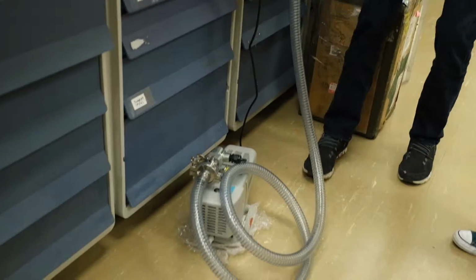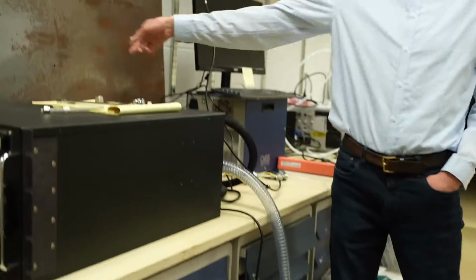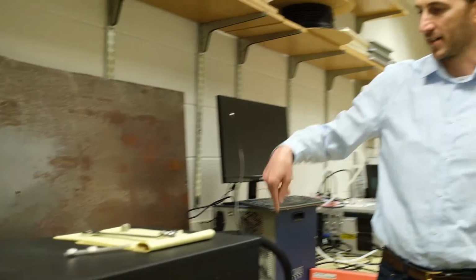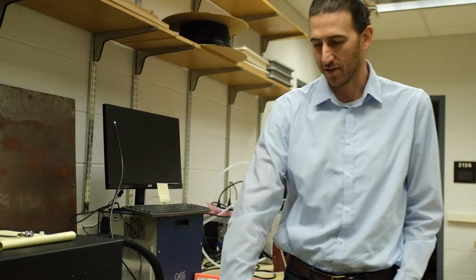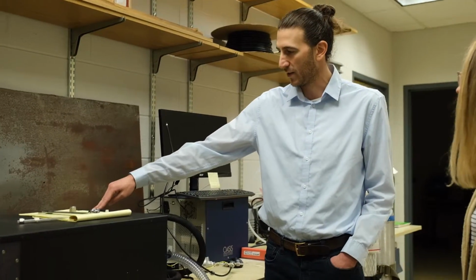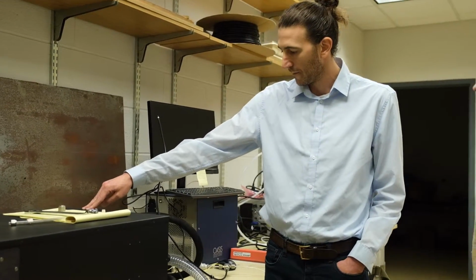So this is the N201. This has been the one that we've actually flown for the project that we're talking about. And so you have the pump. This is how the air gets drawn in. There's an inlet here that would then go outside the airplane, draws the air in through the instrument, and then it actually comes out through the pump. So the pump provides the vacuum power.